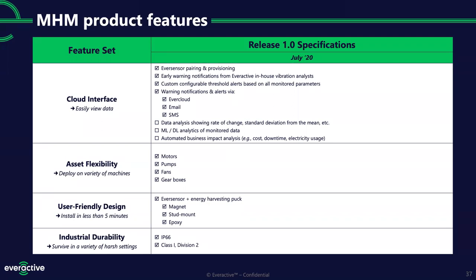You saw the physical install — it's pretty simple and straightforward to get going, applying easily to motors, pumps, fans, gearboxes, really any rotating and vibrating equipment. Right out of the box, these typically go on in under five minutes. Magnetic mounts are the easiest way, but we also offer stud mounts to get up and away from the motor body, or epoxy for high-vibration environments where the magnet could walk. From the time we ship these, they'll be IP66-rated and electrically classified.